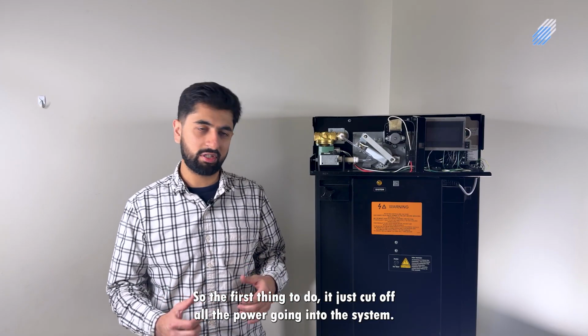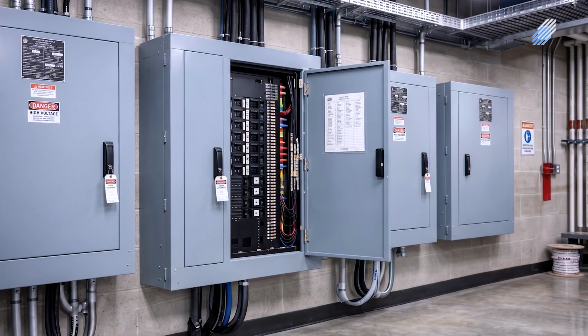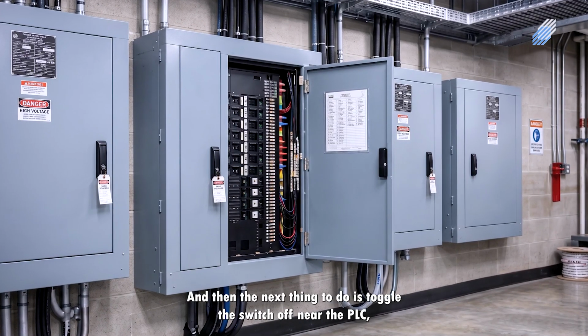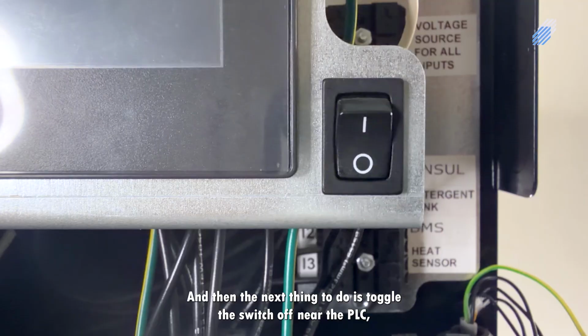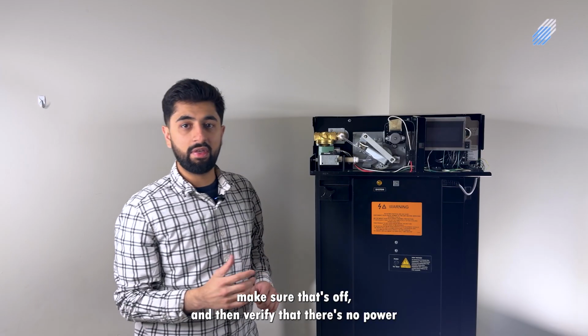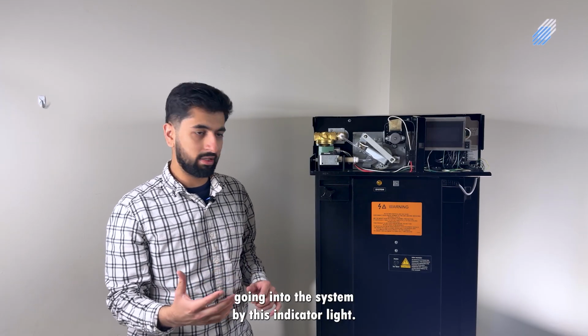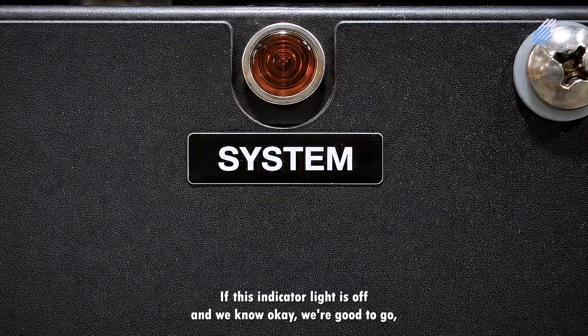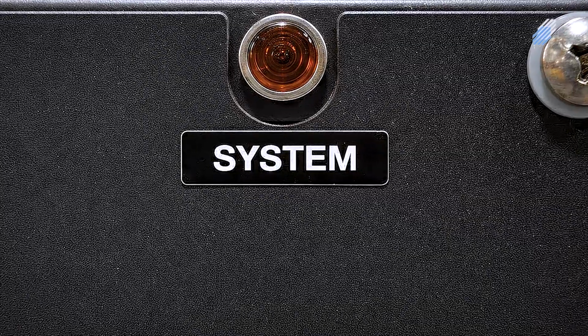So the first thing to do is cut off all the power going into the system. This can be done at the circuit breaker panel. The next thing to do is toggle the switch off. It's near the PLC, make sure that's off. Then verify that there's no power going to the system by this indicator light. If this indicator light is off, then we know we're good to go. There's no power going in.